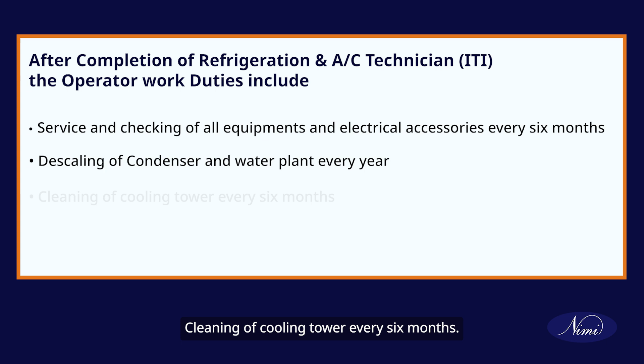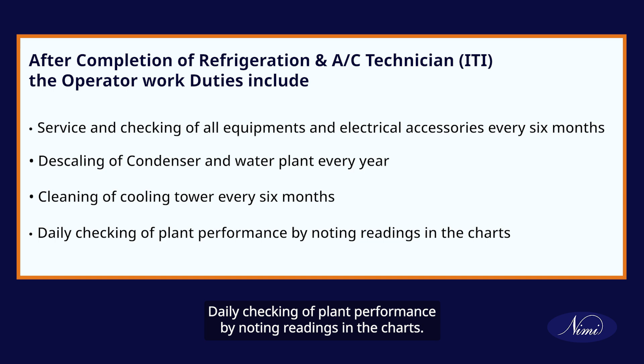After completion of refrigeration and AC technician ITI, the operator work duties include service and checking of all equipment and electrical accessories every 6 months, descaling of condenser and water plant every year, cleaning of cooling tower every 6 months, and daily checking of plant performance by noting readings in the charts.